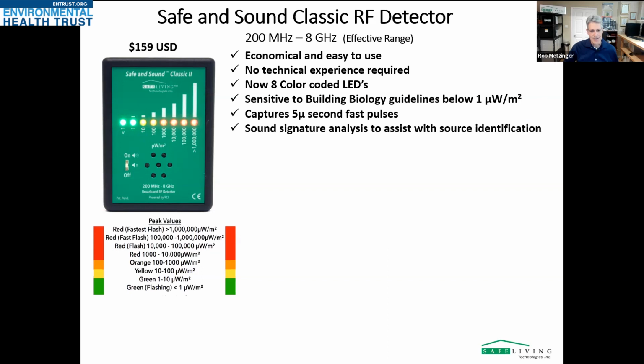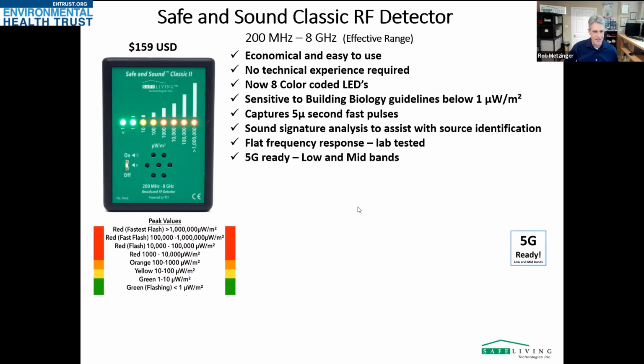And it does have a sound signature analysis to assist with source identification. So that's built into it. You can turn the sound on, you can turn the sound off with this switch here. It has a flat frequency response, and we've definitely lab tested it. It's 5G ready, and what I mean by that is it detects the low and mid bands of 5G.